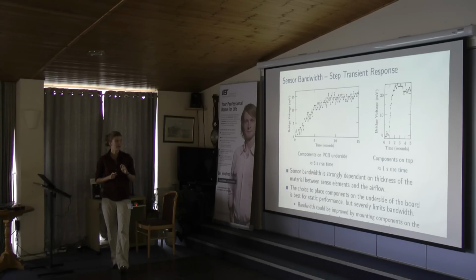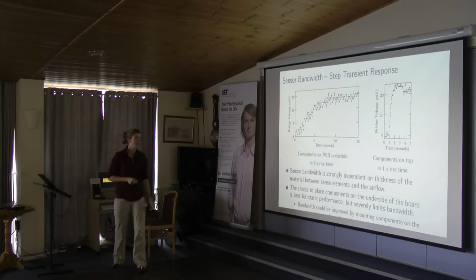We verified that by flipping it over, putting the components on top, where the measurement's not as accurate, but there's no thick insulator between the heater and the fluid, the wind blowing over it. There we see about a 1 second rise time, which would definitely be fast enough for a lot of control systems.